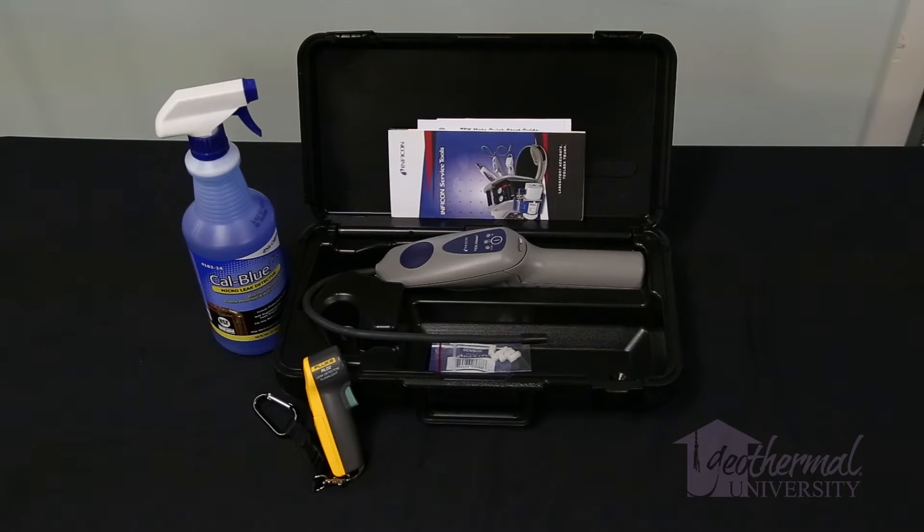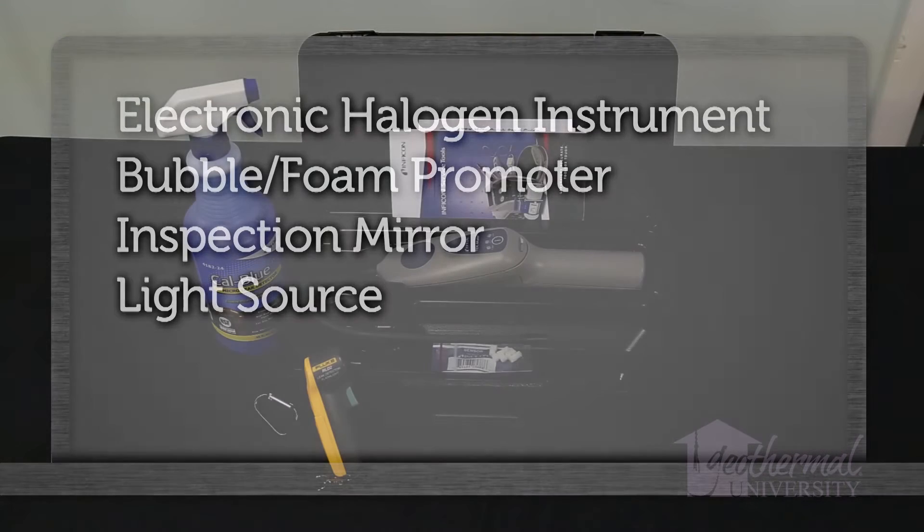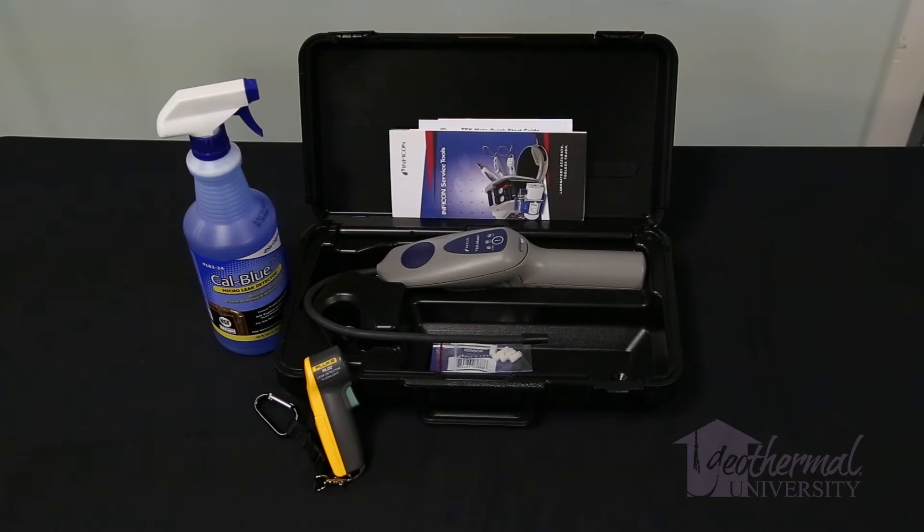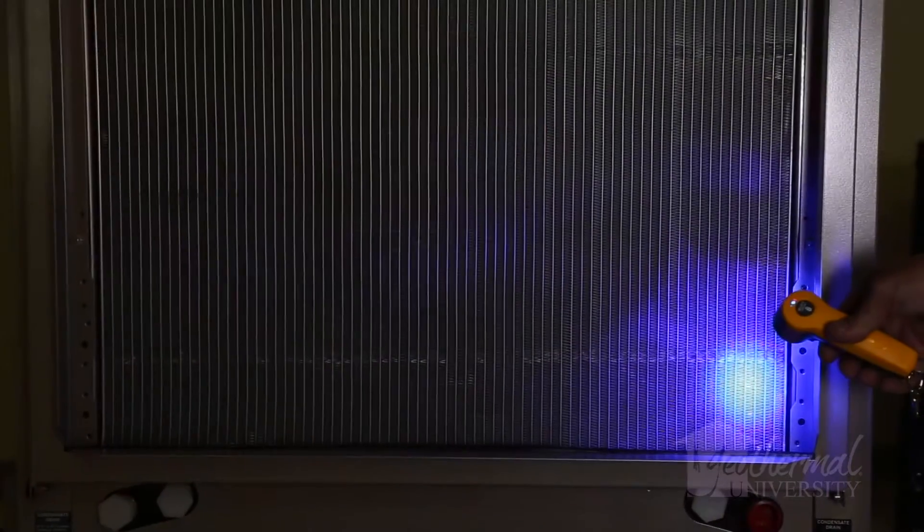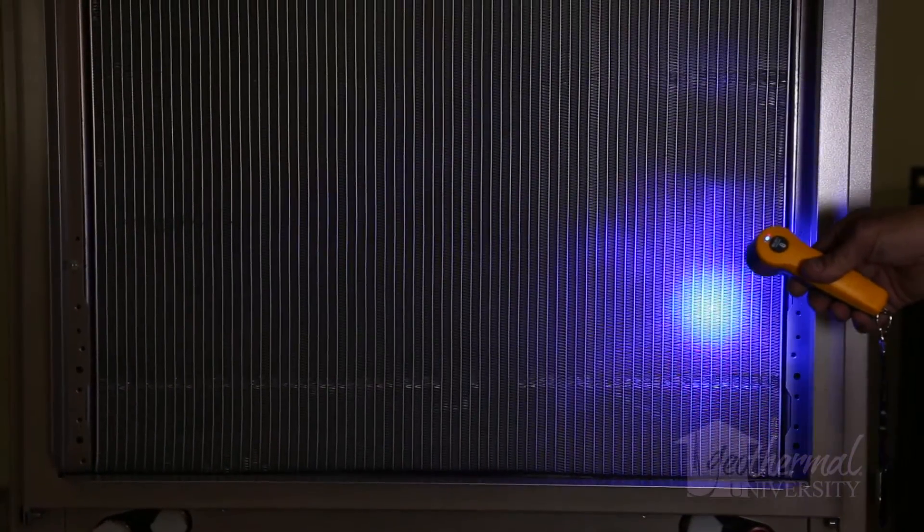Our video recommends a systematic method of search using common leak detection tools. These tools include an electronic halogen instrument having a sensitivity of at least half ounce per year, a bubble or foam promoter, an inspection mirror, and a light source. In addition to the above detection tools, many technicians use fluorescent leak detection.